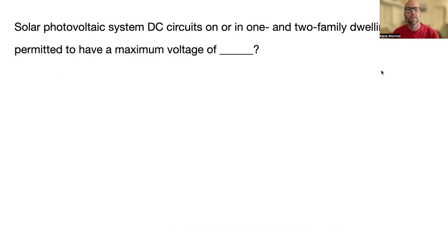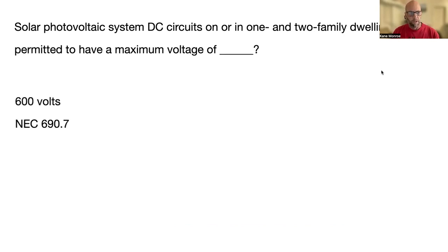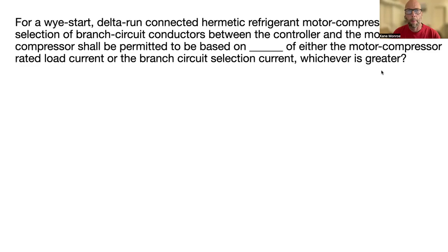Solar photovoltaic systems — DC circuits on or in one or two family dwellings shall be permitted to have a maximum voltage of 600 volts. That's NEC 690.7.